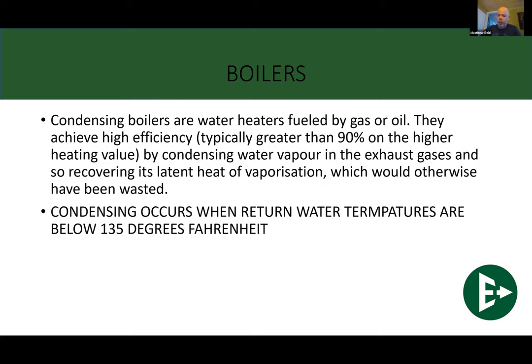So although the burner itself is burning at 90% efficient, we're able to pull out X amount of gallons of condensate per hour, and that adds back into our heat load, and that's how we get the 90%+ efficiencies. It has nothing to do with combustion efficiencies. It's strictly with regards to how much we can make this thing sweat. Some heat exchangers do a better job at it than others.